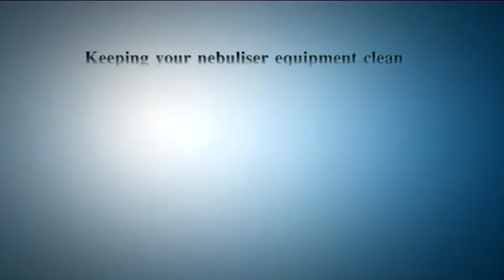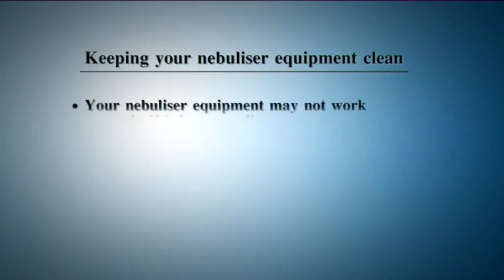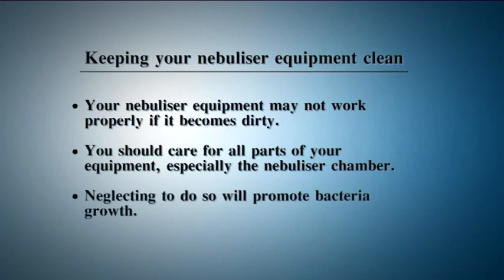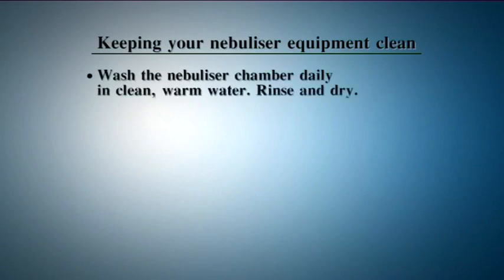Keeping your nebuliser equipment clean. Your nebuliser equipment may not work properly if it becomes dirty. You should care for all parts of your equipment, especially the nebuliser chamber — neglecting to do so will promote bacteria growth. Wash the nebuliser chamber daily in clean, warm water. Rinse and dry. Wash the face mask or mouthpiece after use in warm water. Rinse and leave to dry.